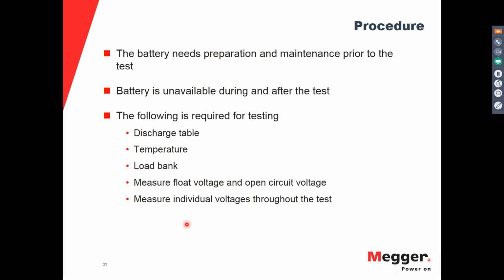To perform the test, you need the discharge table. So you need to know what are the recommended manufacturer discharge rates. You need to define what's going to be your time for running the test. You need to measure the temperature before starting the test. You need to consider your load bank, the test instrument that you're going to be using. You need to calculate how big it's going to be. And you need to perform some voltage measurements before the test and during the test.